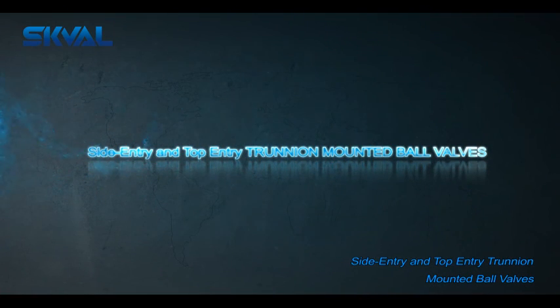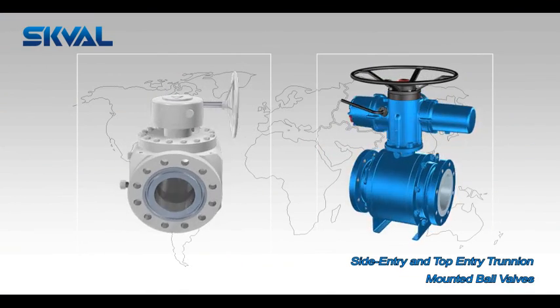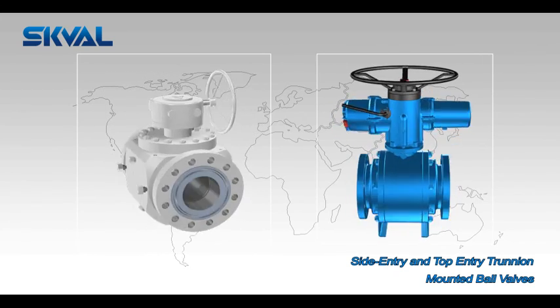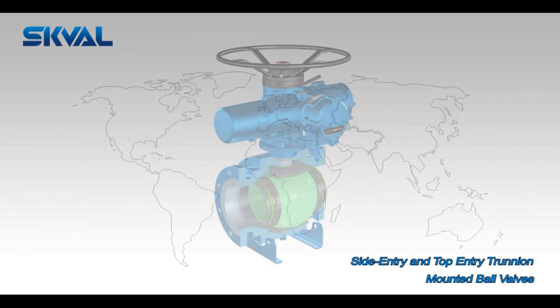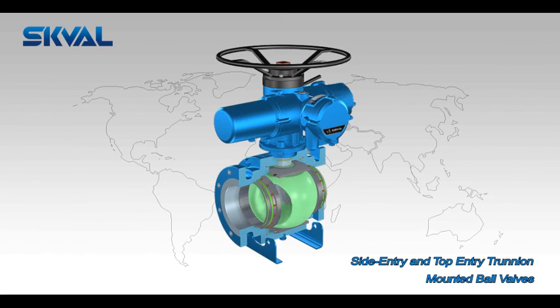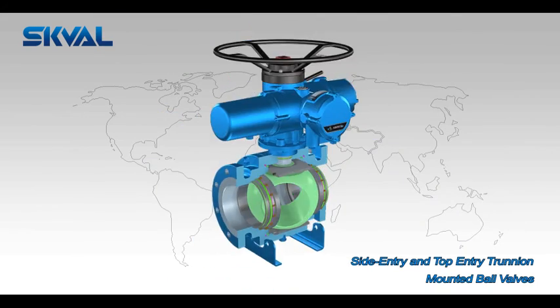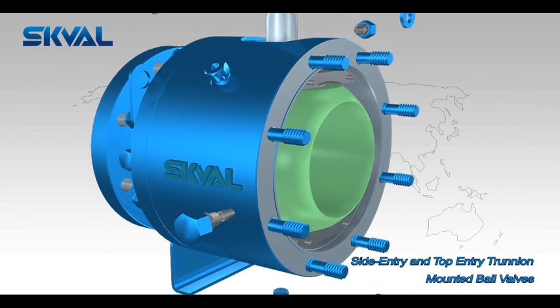SKVAL designed the Side Entry and Top Entry Trunnion Mounted Ball Valves to assure bi-directional sealing of the valve with two independent floating seats. The design of these seats minimizes the torque required to operate the valve without losing the sealing power. This sealing power is assured from zero differential pressure up to the valve's maximum rated pressure.